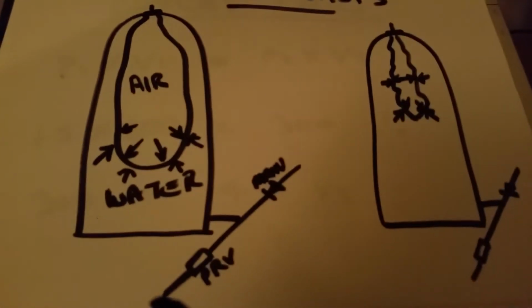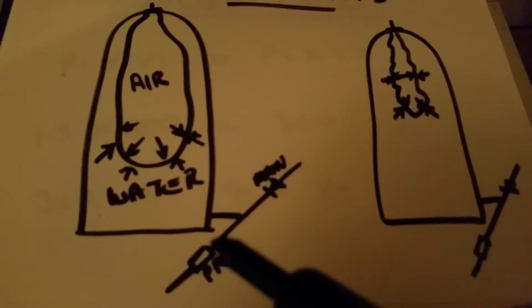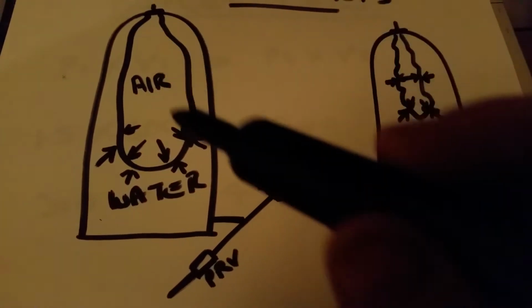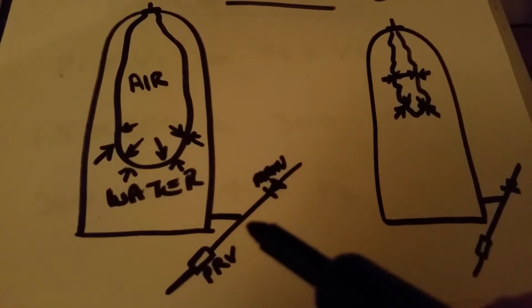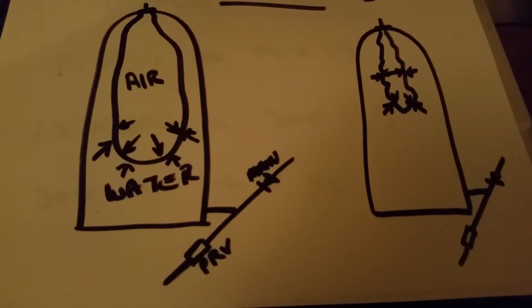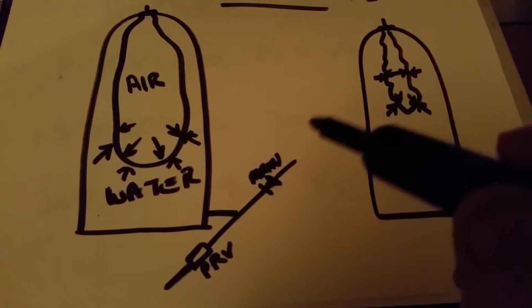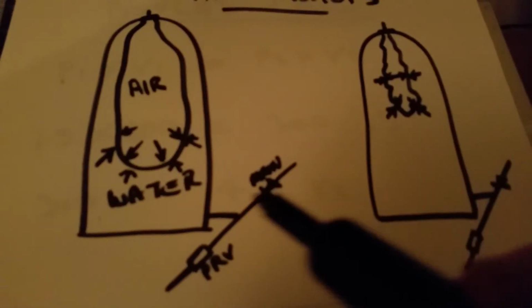Open a tap, and the air pressure forces the water back out and will deliver the water at the standing pressure of the main, but on a declining pressure. So as the bag expands open, pressure drops and we'll get a sort of full pressure burst and a gradual drop off. But we could, for instance, have a standing pressure here that I'm going to use in my example of 4 bar, but actually have a very low dynamic pressure and a very low flow due to restricted pipework.